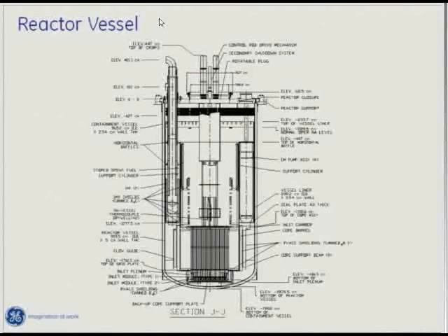This is a cross-section of the reactor vessel. These are electromagnetic pumps that have no moving parts. The sodium takes a suction at the bottom of the reactor core, flows up by the fuel — which is HT-9 cladding with the metal fuel inside — goes into the top of the intermediate heat exchanger, comes back down, and gets recycled. Up here is where fuel elements, after they've been in the core, are stored — providing cooling and reflection to reduce neutron flux against the reactor vessel. There's an in-core refueling machine on top. The reactor vessel is about 60 feet tall, about 30 feet in diameter, and made out of 316 stainless steel, about 2 inches thick.